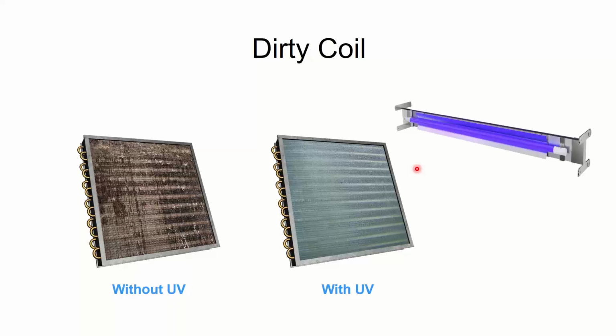So what the hell is a UV light good for? It's good for keeping coils clean. That's all it's good for. Putting UV light in your return duct is stupid. Putting it in your supply duct is stupid. Stupid's a technical term. UV lights need to be shining on the coil because the coil doesn't move.